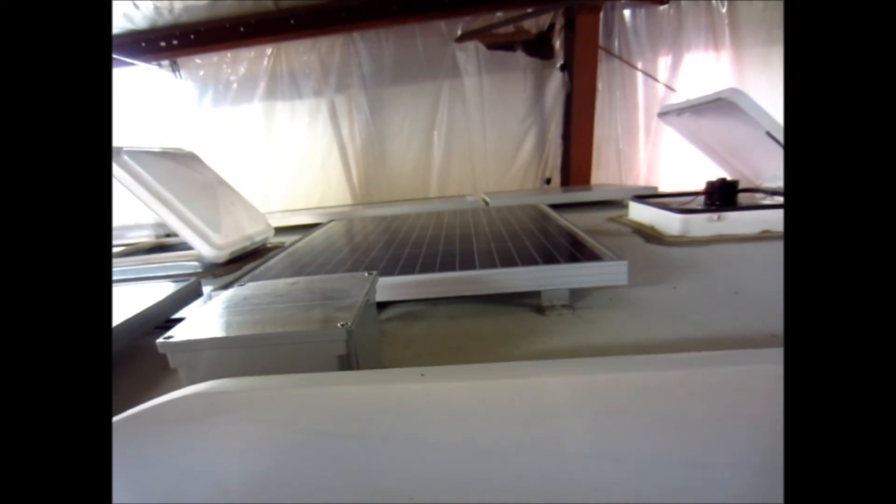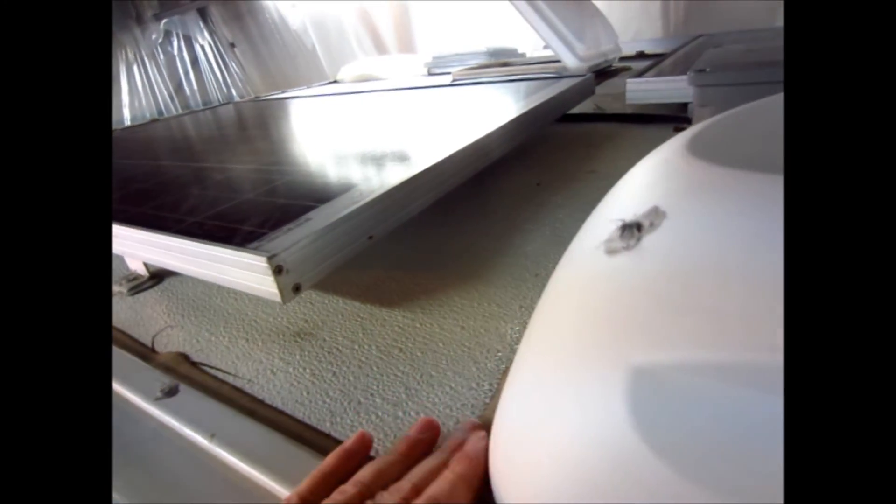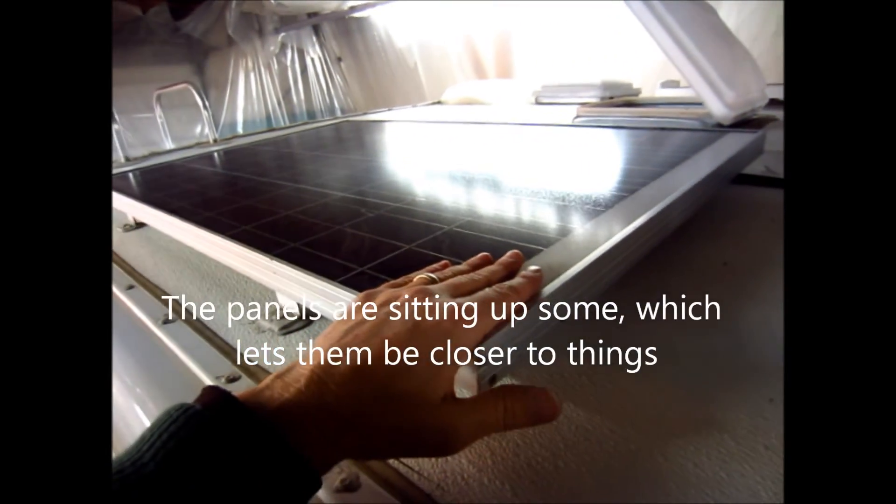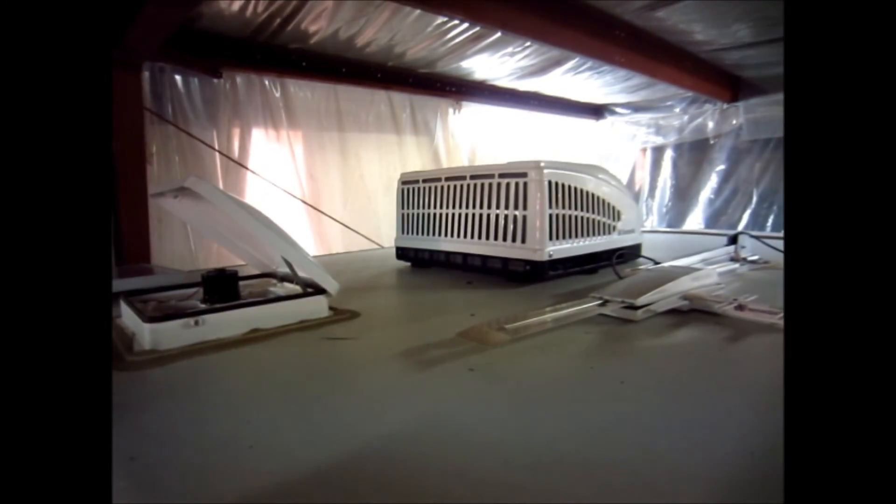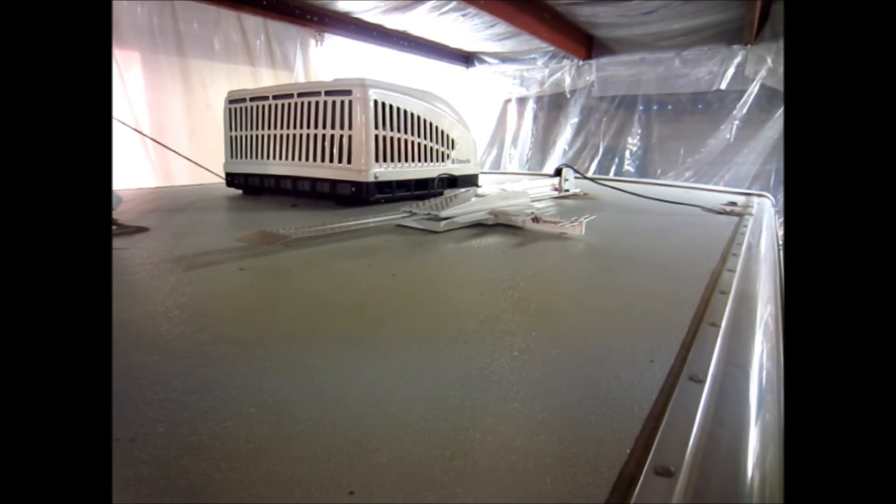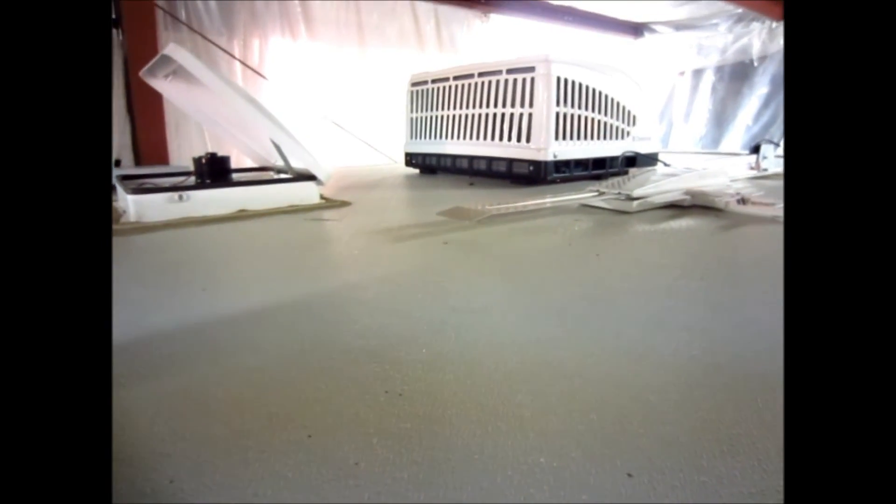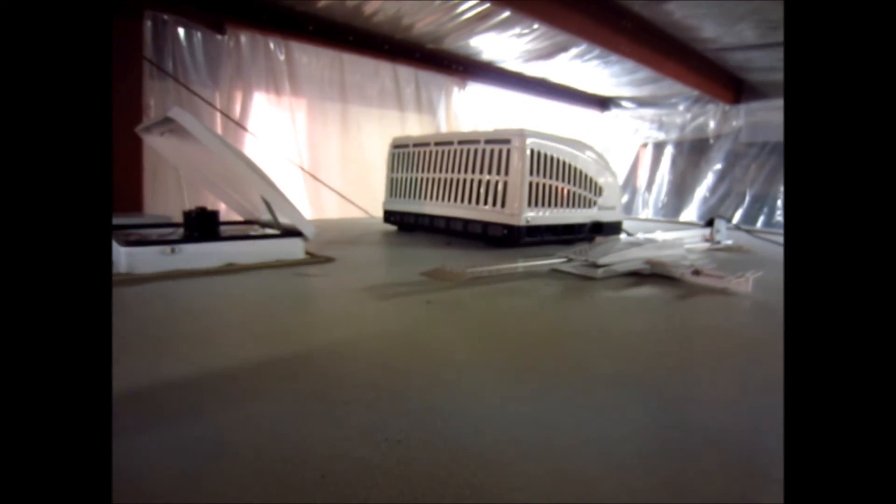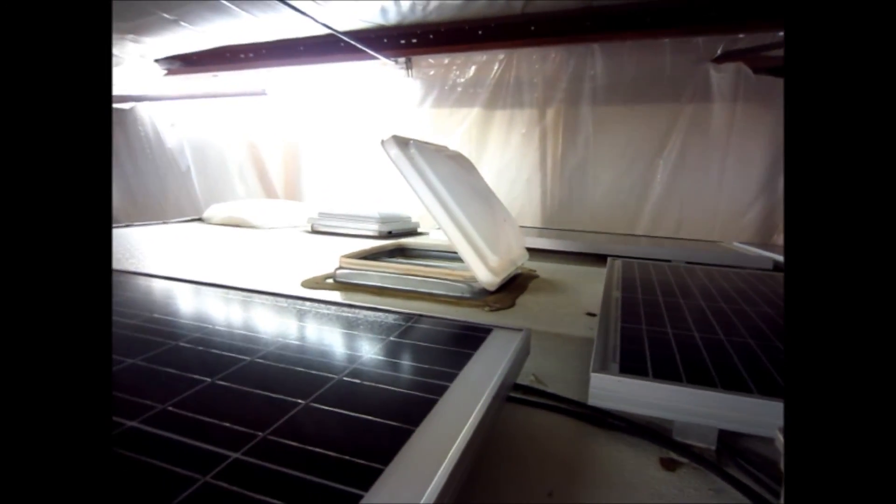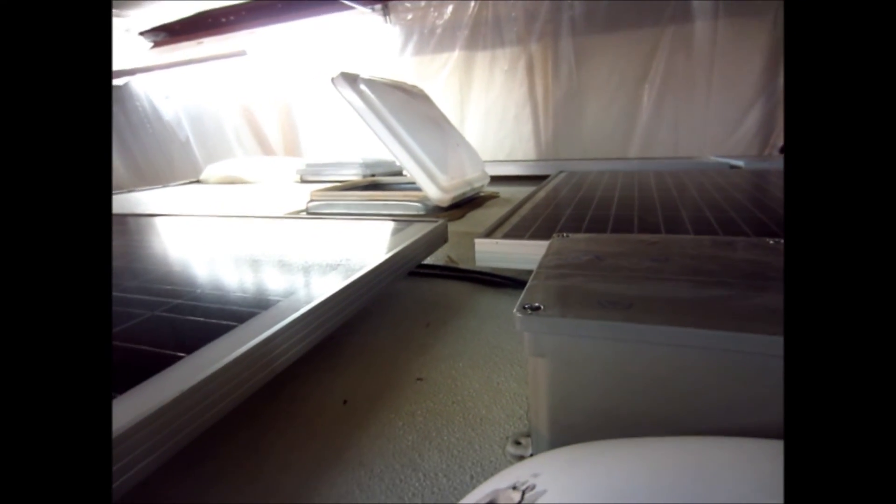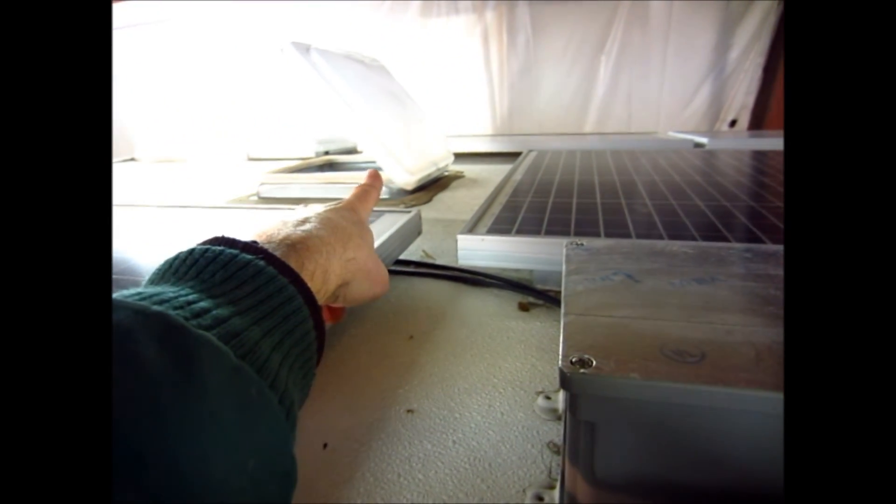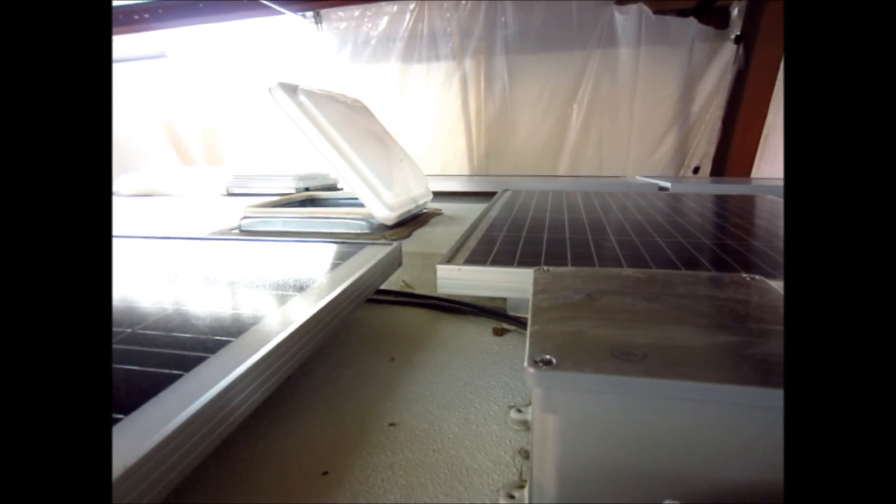When you're locating your panels you want to be at least as far from an object as the object is tall. That'll give you a 45 degree angle of sun that's still going to hit the panel. If you get any coverage on the panel, even this much, it can kill the output of the whole panel and that would be a shadow doing that. So I found out where those things peaked. I stayed away from the air conditioner as it turned out. If you have an antenna like this that goes up in the air three feet or so and then can swing around in a big arc, just the fin from the one end of the antenna can cast a shadow. So you'd have to be very aware of all the places that that shadow could cover at a 45 degree angle. But anyway, that's my basic design principle. Different people have different ideas. The farther away you get from an object, the less likely you are to have shade. If you were to put this panel right up close to that vent, there would be times when it would be shaded and would be worthless.